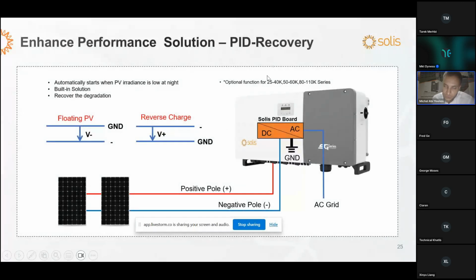One of our features I would like to talk about is the PID-Recovery. Throughout the day and throughout the years, some of the electrons on the negative side of the cells of the panels will be lost. So the PID is like sending a reverse voltage to the panels in order to maintain them, to compensate for this loss of electrons on the DC side. This can be programmed, and this feature can be activated on the inverters from 25 kilowatt till 100 kilowatt, and also for our utility scale inverters.